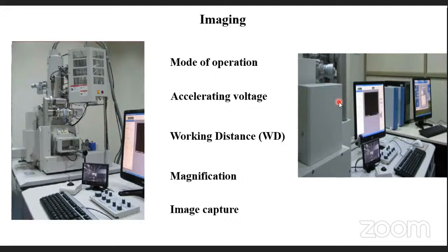Secondary electron mode is more than enough for basic analysis. For composites requiring elemental contrast on your image, go for backscatter electron imaging. For knowing which elements are present in your sample, go for EDS — energy dispersive spectroscopic analysis, which uses the X-ray detector. You also need to decide the acceleration voltage. For metallic samples we can go up to 25–30 kV, but for biological or polymer samples we don't go beyond 5 kV, as higher voltage may damage the sample.